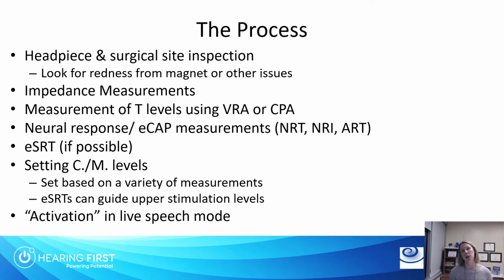So the next thing we'll do is something called impedance measurements. That's looking at how the device is in the cochlea. My description of it for families is that it's their fingerprint of their ear. When we first measure impedances, when they first get the device activated, or if they haven't worn it for a period of time, those impedances are higher. But typically they start to flatten out, and by 3 to 6 months, they're pretty much consistently about the same.